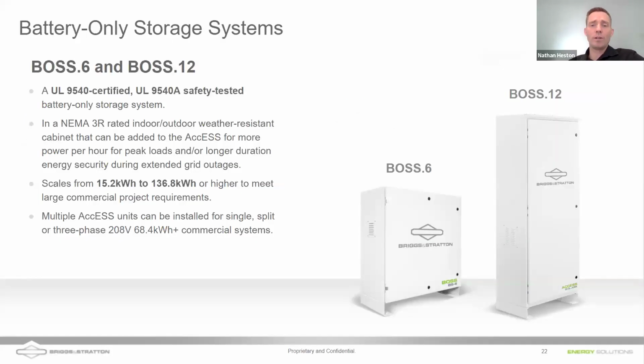If you are going to be installing outdoors with either the Phi or the SimpliPhi batteries, because these are not outdoor rated batteries, you'll need to put them in an enclosure. These are NEMA 3R enclosures. They're UL certified. We do a lot of safety testing on all of our equipment, our batteries, as well as our inverter and our battery cabinets. What you're seeing on the screen is a Boss 12 cabinet and a Boss 6 cabinet, which will fit 6 and 12 of those 3.8 batteries, either the communicating or the non-communicating.